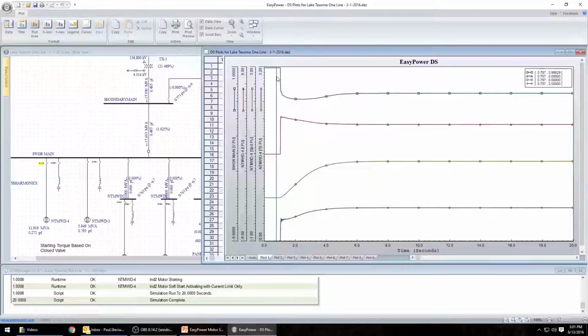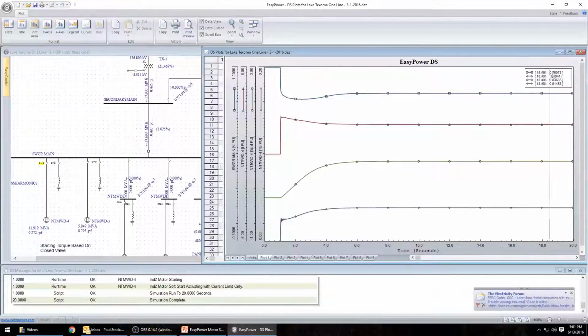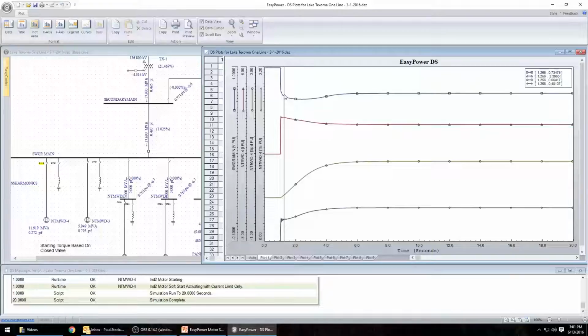The top graph represents the system voltage, or the 4160 volt voltage, and it drops to roughly 0.71. In the top right screen, here you can see the voltage is basically 0.76 out here. So the voltage drops to roughly 0.73. The next curve is the starting current of 3.4, and that's 3.4 per unit starting current for that motor. And you can see at the starting point that the motor will ramp up in speed, but it never exceeds 0.836 per unit. And the bottom curve represents the electrical torque to the motor. So in this situation, the motor did not start.